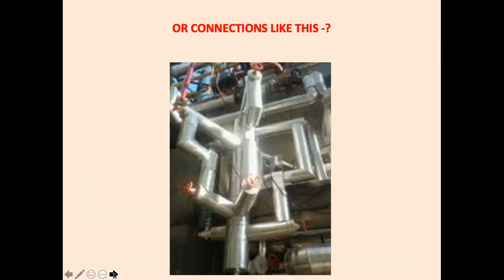Don't do piping like this with right angle bends. This is wrong piping. And just now I'm facing a problem in one of the installations where this type of piping has been done for the float switches. Now we have to change. The float switches are not operating because the pressure drops in these lines are indicating different operating conditions for the float switches and for the vessels. So do the simple piping.